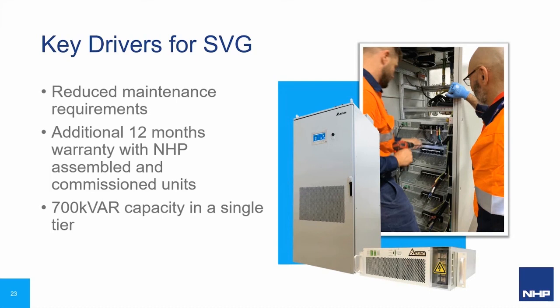But at the end of the day, you were looking at anywhere from about 2.5 years up to, say, about 3.5 years payback, which they were quite happy with, and when they looked at the cost of what it was also even to attempt to get their existing systems up to where they needed to be, the SVG was the clear winner in that scenario. Now, as far as how it was delivered, a local board builder provided the end user any modifications to accommodate larger breaker ratings, or even a breaker that may have not existed. If some areas didn't have a cap-based system, to do those mods.